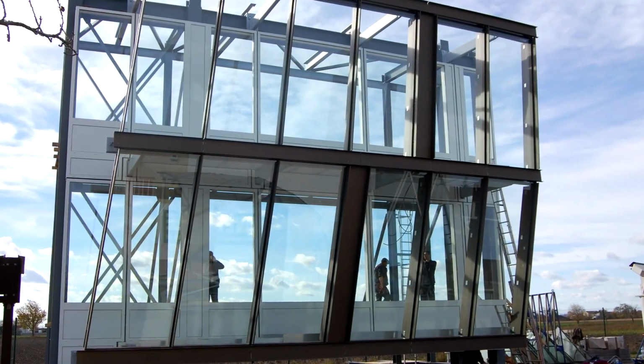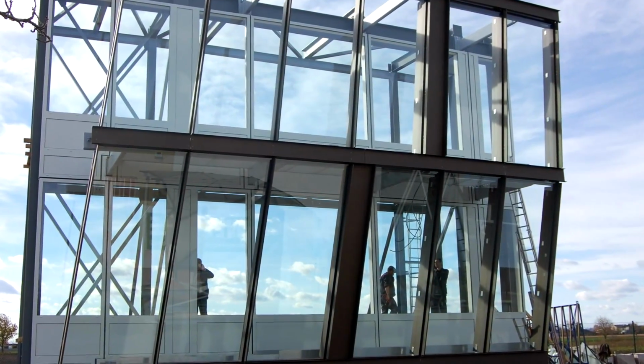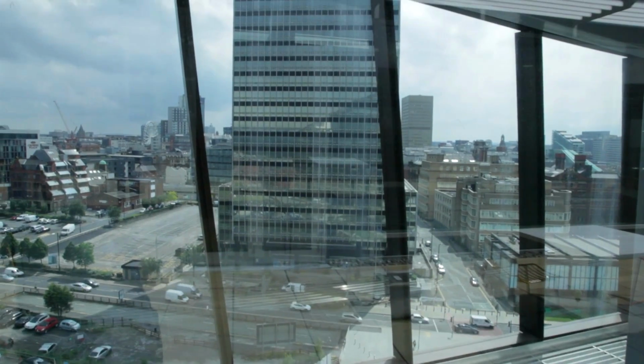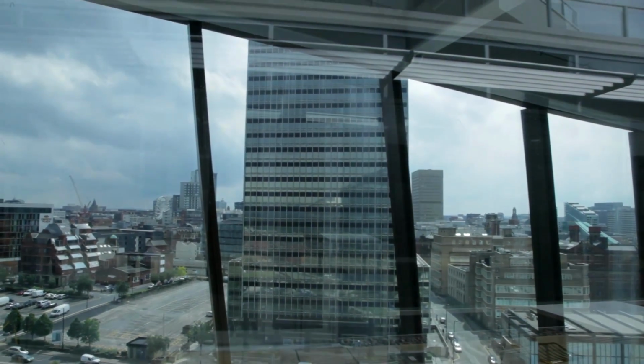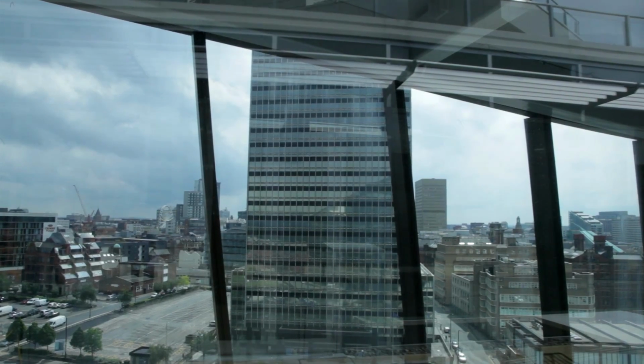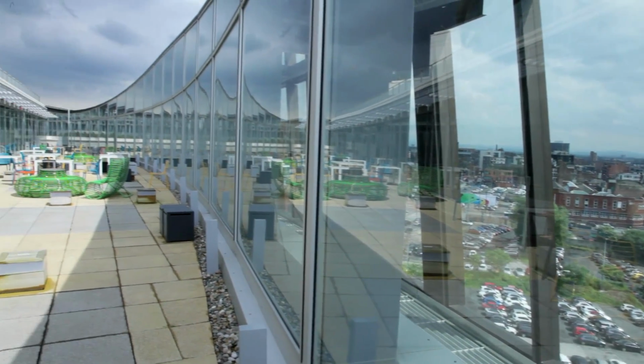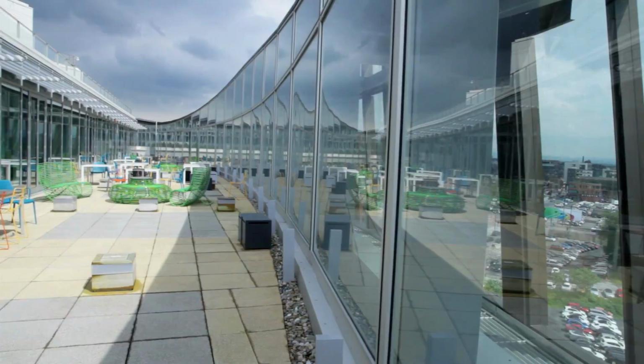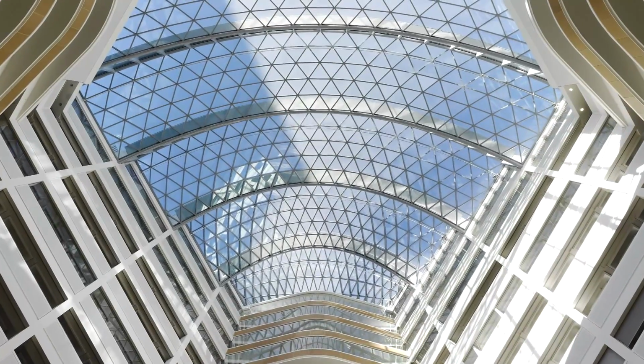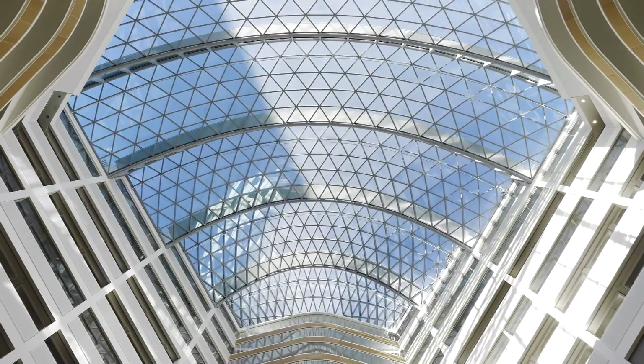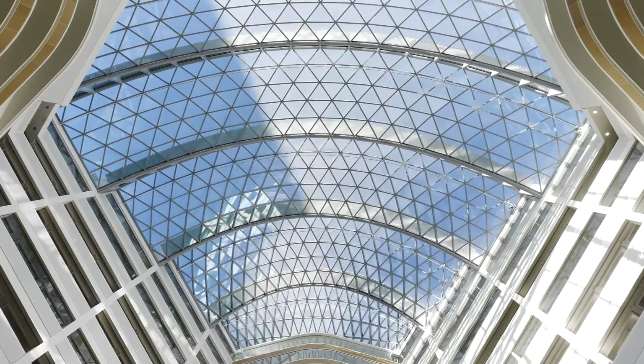The outer skin of the facade is single glazed. It's a weather line, but it's not the thermal line. So really that's the piece of the facade that seals the building and helps to seal in that warm body of air. So that effectively acts as a big blanket which helps to keep the building warm in the winter, and in the summer we can open the vents at the top of the facade and that allows free flow of air to help keep the building cool.